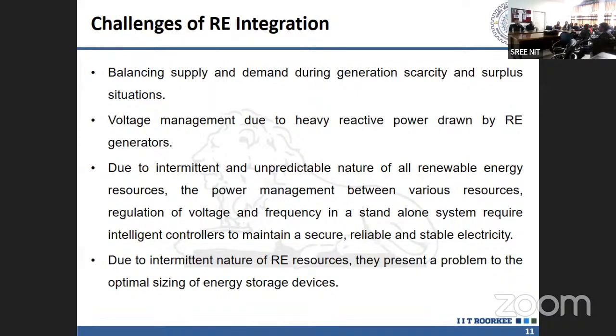MPP we will discuss later, that doesn't matter here. MPP will be required when the load is more than the supply—then it matters whether you are working at the maximum power point or not. If you don't have that much load, this will give rise to issues. In light load conditions, the receiving end voltage will become higher than the sending end voltage, and sometimes you will get very high voltage at that equipment, which can cause damage.